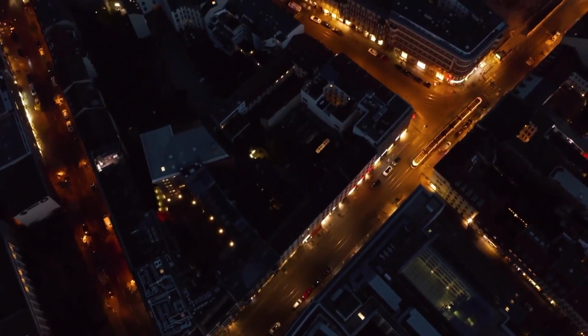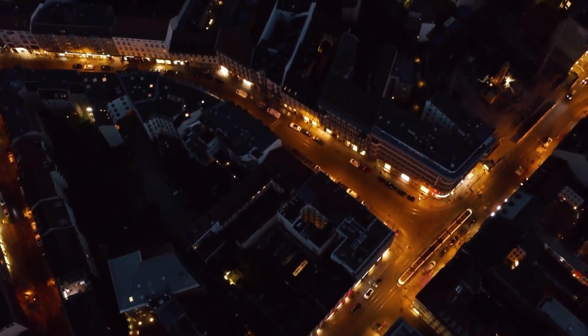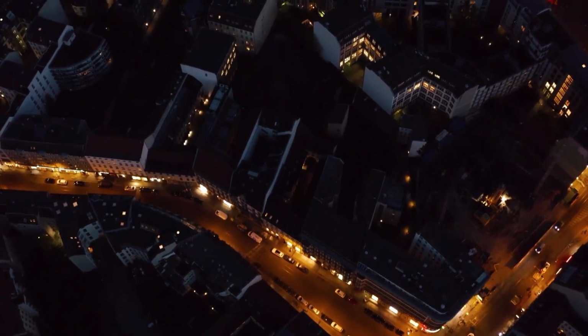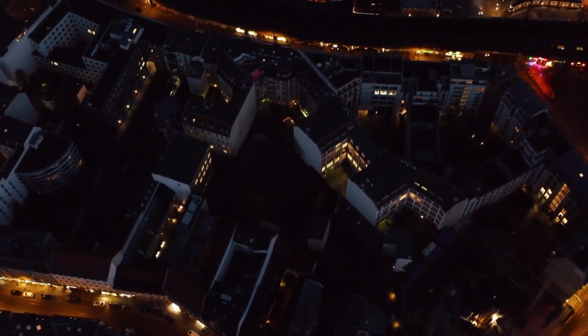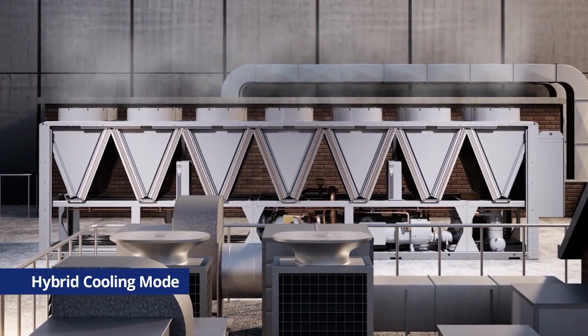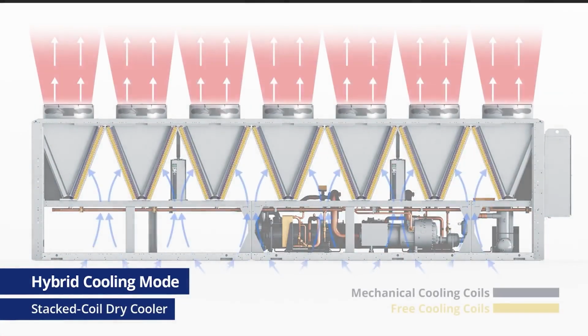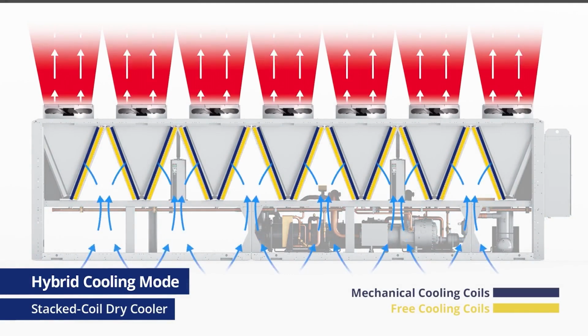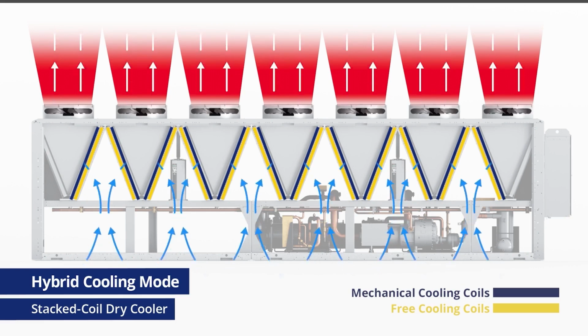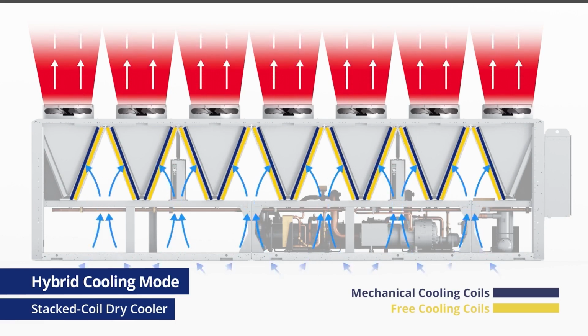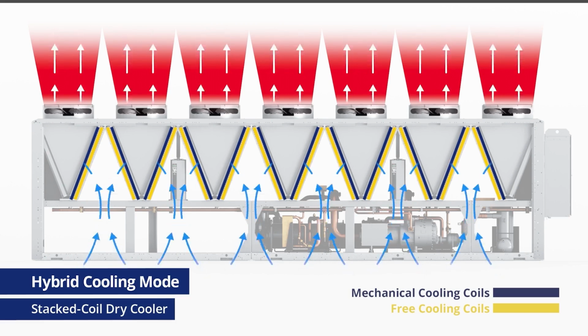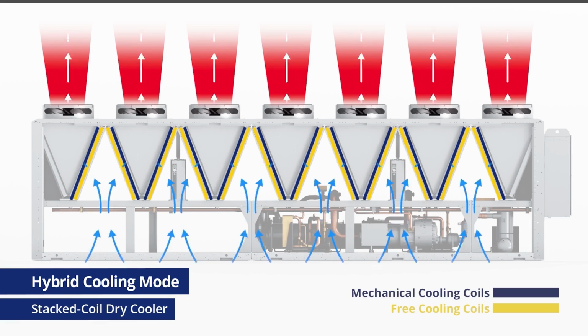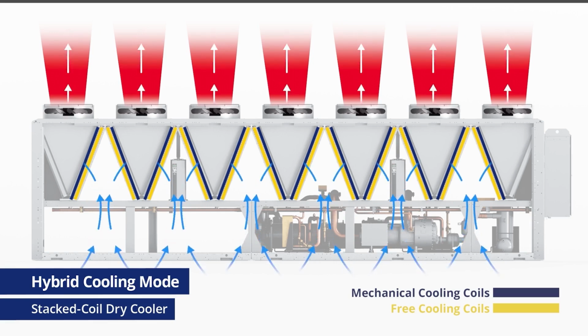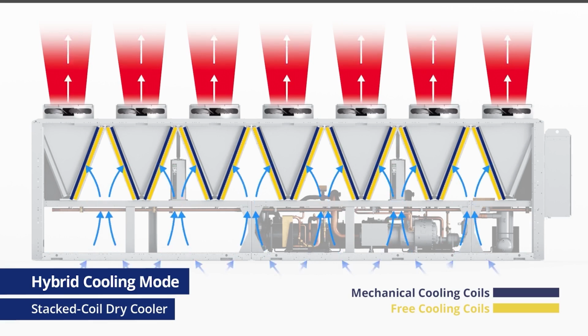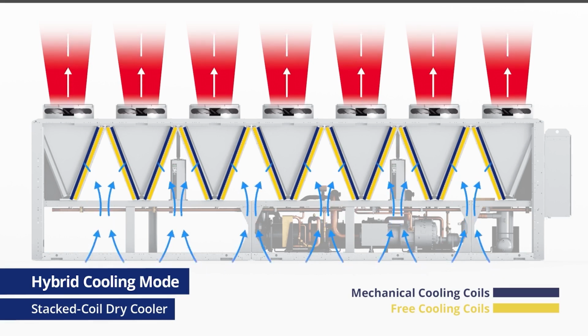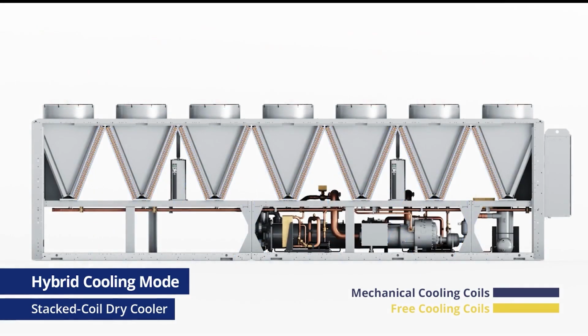Even when the ambient temperature isn't low enough for free cooling only, some free cooling is still possible. This requires hybrid cooling mode, where both sections of the chiller work in tandem. With the stacked coil design, air needs to flow over both sets of coils. This presents a problem for the fan control system. The free cooling coils want as much air as possible to maximize performance. Conversely, the mechanical cooling coils want to lower the fan speed to ensure the fluid doesn't get too cold, missing the set point and shutting down the chiller. As a result, the system can become less dependable with frequent nuisance trips. In addition, the system fails to make the most of the free cooling opportunity.